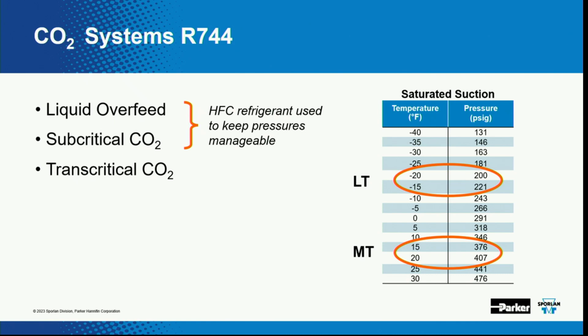In these first two, as shown here, liquid overfeed and subcritical, these still require an HFC chiller, if you will, to do the primary cooling of the CO2 before that gets fed out to the cases. So we'll get into that.